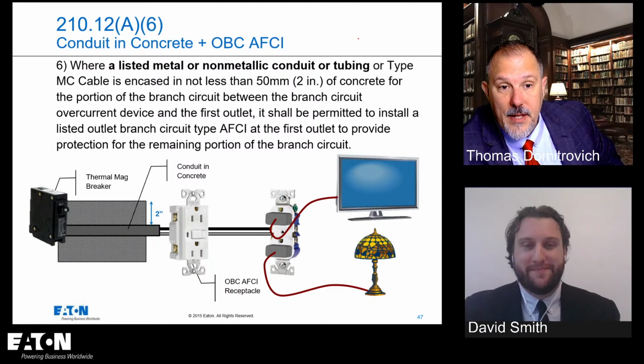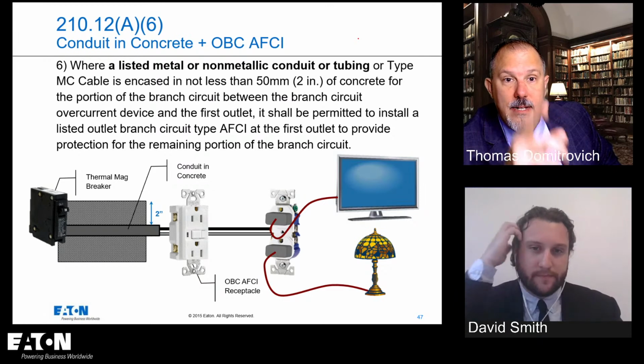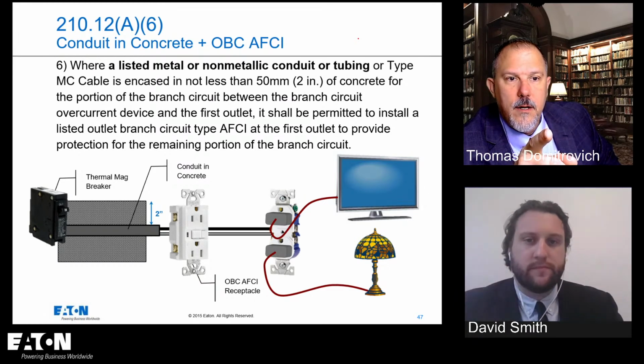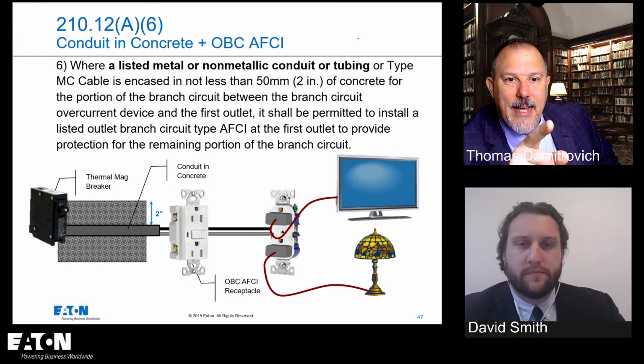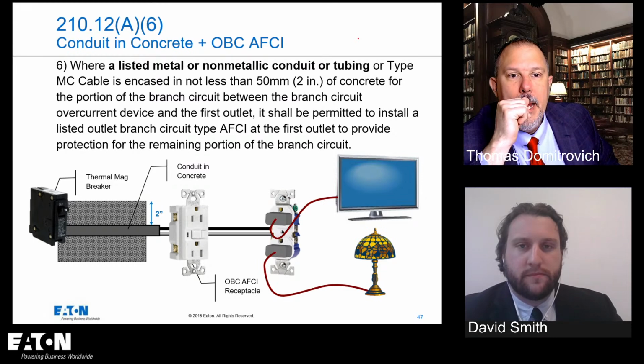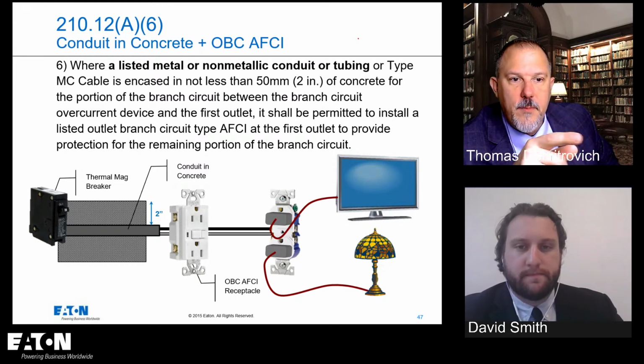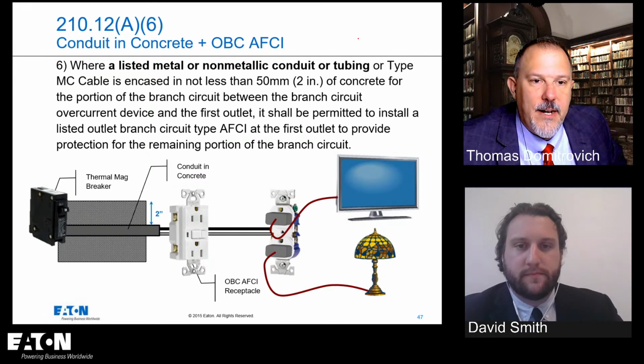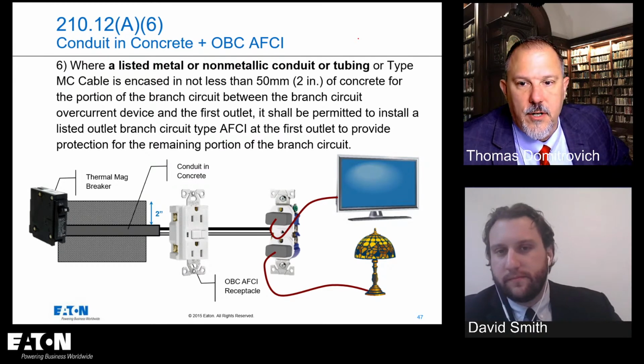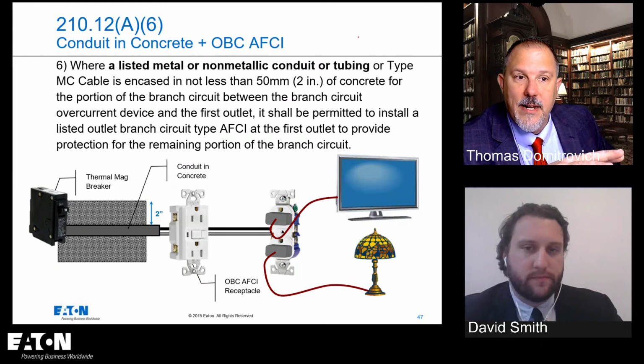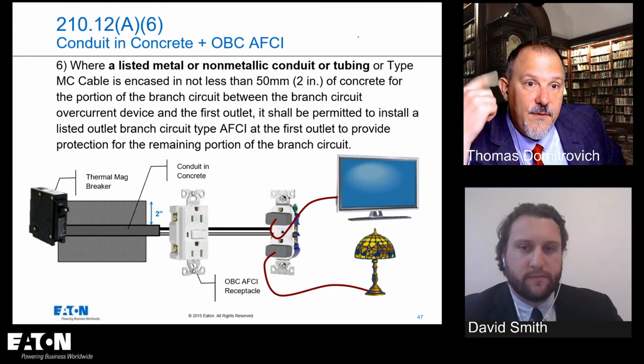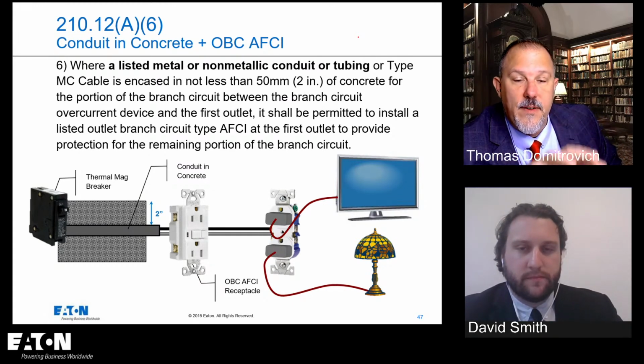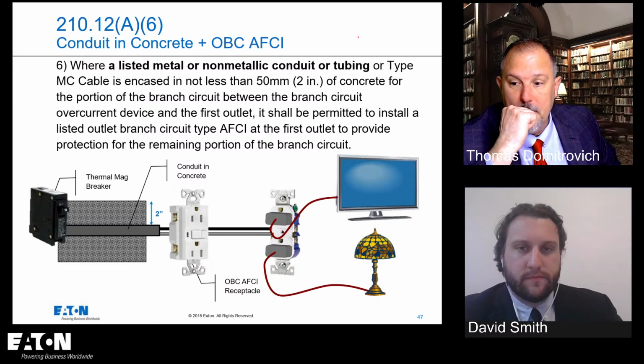Right. And the other is having listed the MC cable encased in not less than 2 inches of concrete for the portion of the branch circuit between the branch circuit overcurrent device and the first outlet. It shall be permitted to be installed in a listed outlet branch circuit AFCI at the first outlet to provide protection for the remaining portion of the circuit. So I can use a standard thermomagnetic breaker in options 5 and 6 as long as I'm providing protection of that home run circuit.